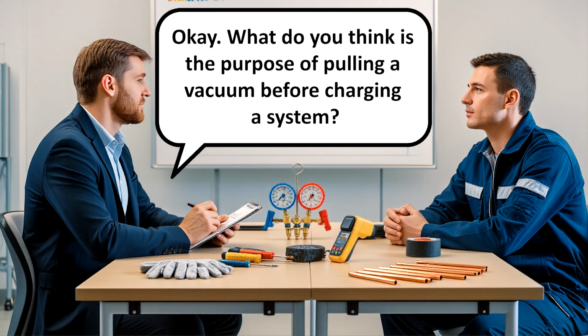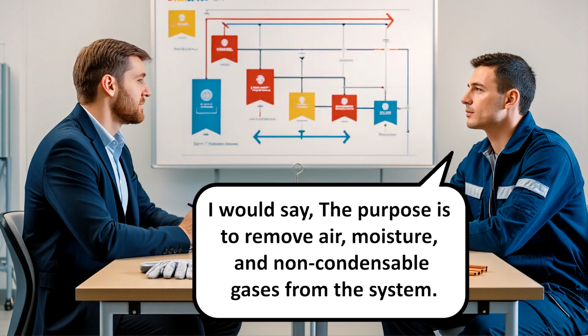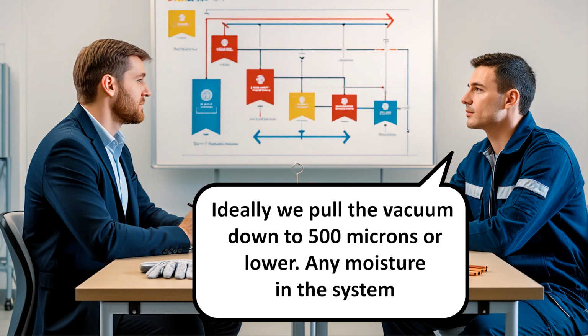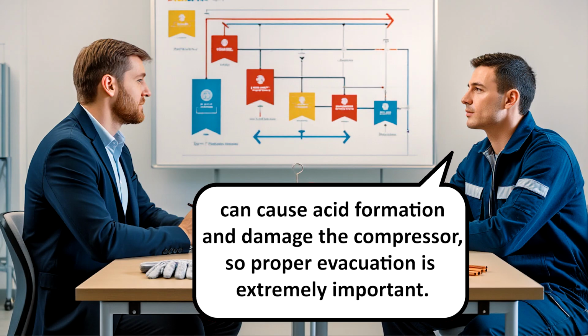Okay, what do you think is the purpose of pulling a vacuum before charging a system? I would say the purpose is to remove air, moisture, and non-condensable gases from the system. Ideally, we pull the vacuum down to 500 microns or lower. Any moisture in the system can cause acid formation and damage the compressor, so proper evacuation is extremely important.